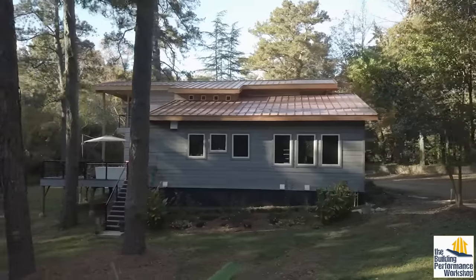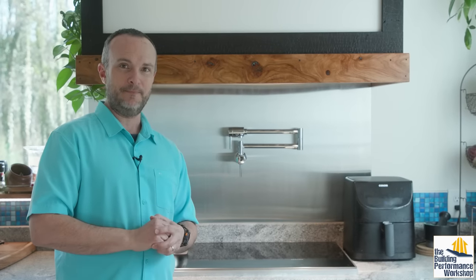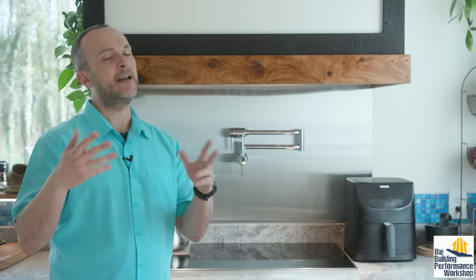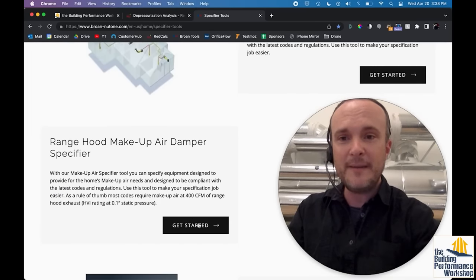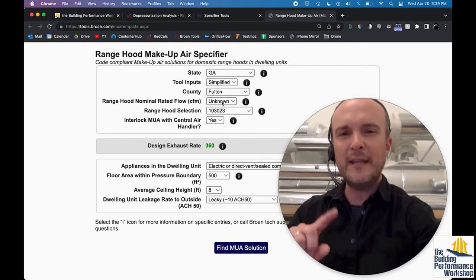This house we built — our forever home — has a blower door test of 300 CFM. So if I installed a 350 CFM exhaust hood, code says I don't need makeup air. But in reality, that hood is moving more air than the blower door test on this house, so every time I ran it I'd essentially be doing a blower door test. You need to use actual tools and calculators — I'm linking a video on an online calculator from Broan — to determine when you need makeup air, how much, and whether passive or active is appropriate.